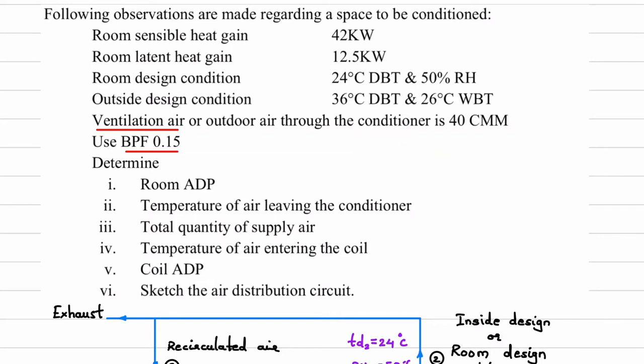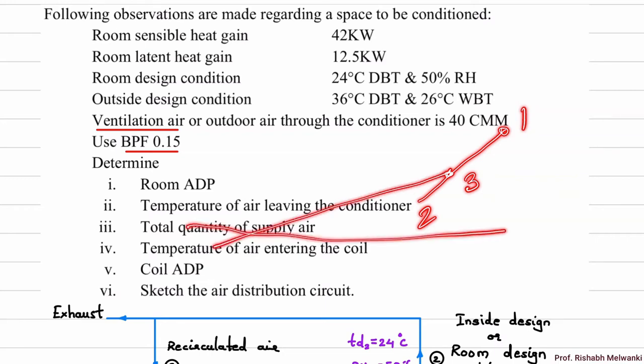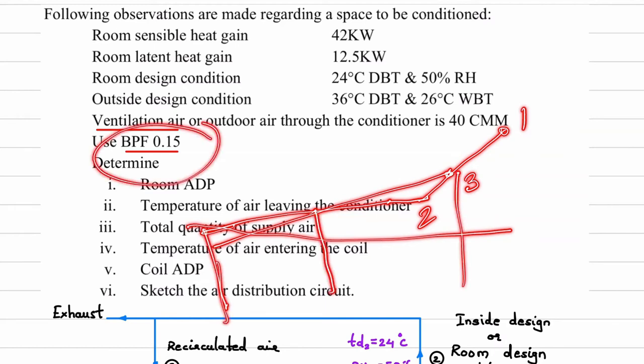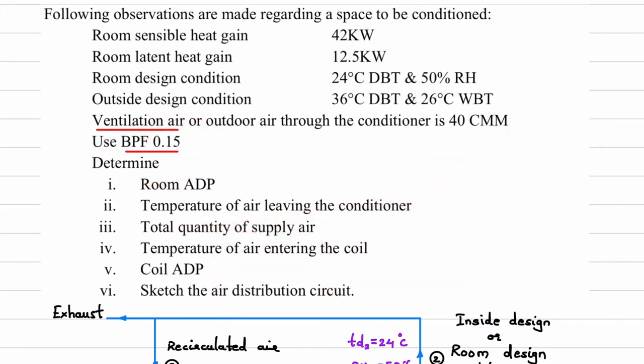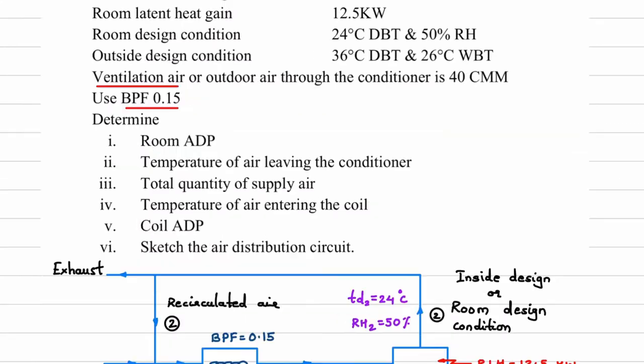Since ventilation air is given, we will calculate ERSHF. We cannot get mixing point 3 because the mixing proportion is not given. In previous numericals, the mixing proportion was given (e.g., M_dot_DA1 is 40% of M_dot_DA3), so point 3 could be found and bypass factor used on the GSHF line. Here, we don't have point 3, so we will use the ventilation air data to calculate ERSHF instead.